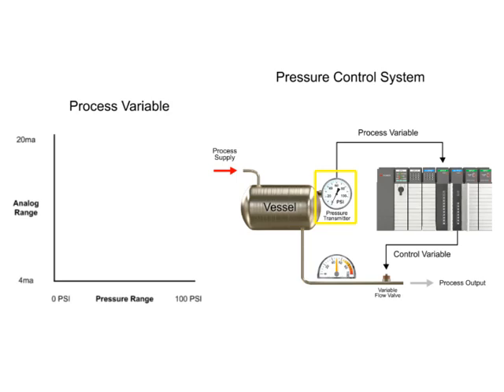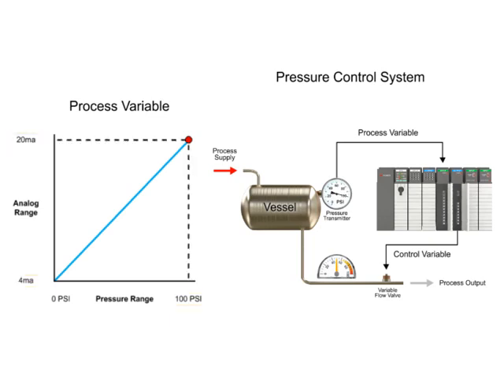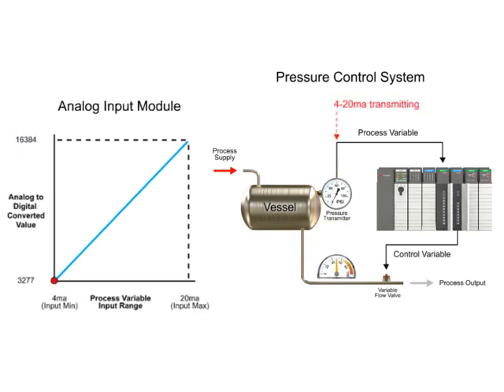The pressure transmitter, identified as the process variable, converts 0 to 100 PSI to a 4 to 20 milliamp signal. With a linear relationship, 0 PSI measured at the transmitter produces a 4 milliamp signal, and at 100 PSI a 20 milliamp signal is produced. The analog input module converts the 4 to 20 milliamp signal to a digital value ranging from 3,277 to 16,384. A 4 milliamp signal results in a value of 3,277 and a 20 milliamp signal results in a value of 16,384.